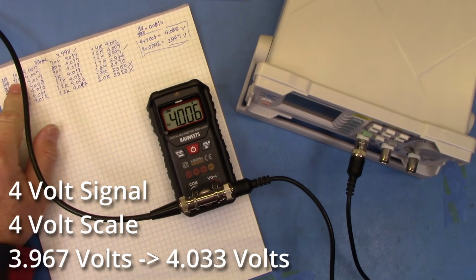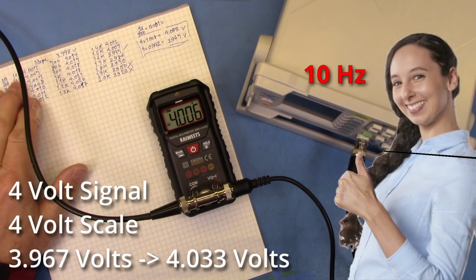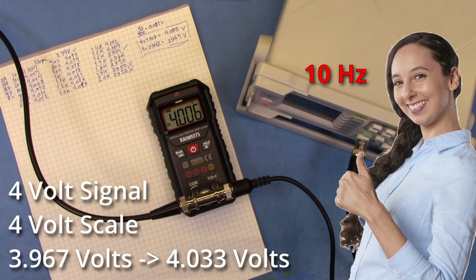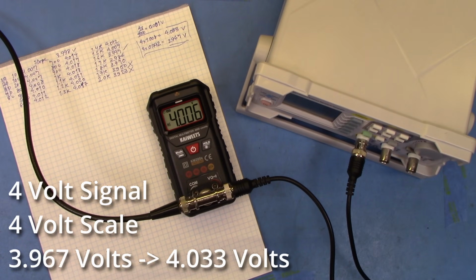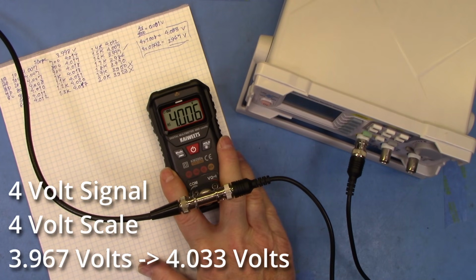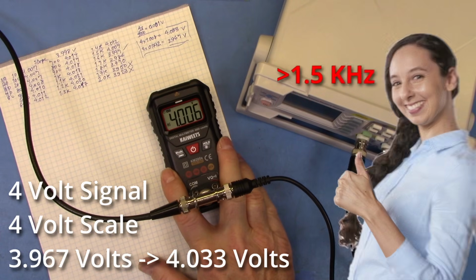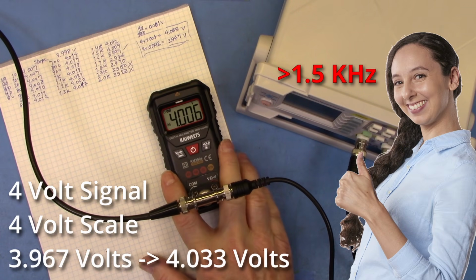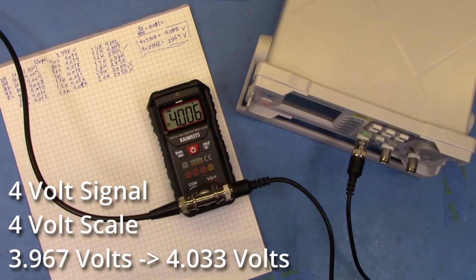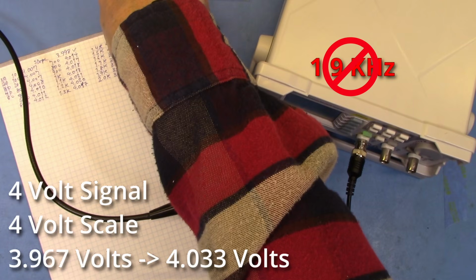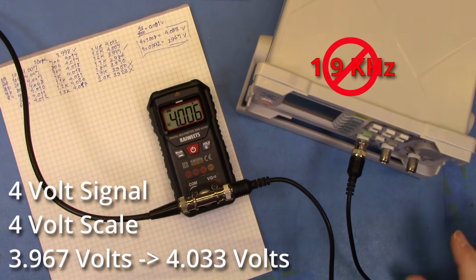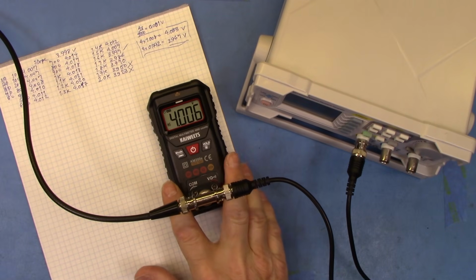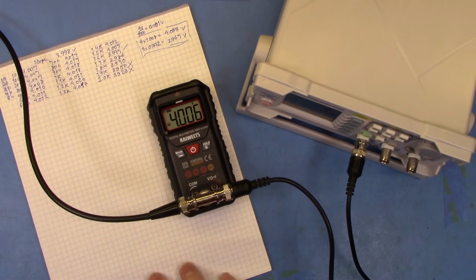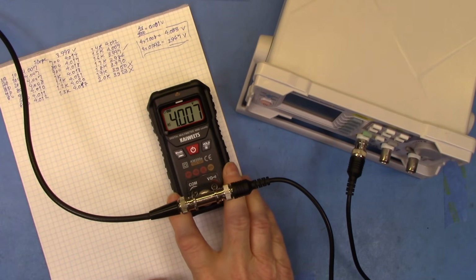So we're assuming the bottom end capability of the KAiWEETS is going to be around 10 hertz. Then from there I moved up in frequencies, and I discovered this meter stayed well within tolerances all the way up to and past 1.5 kilohertz. That's not bad at all. But it dropped out of tolerance at 1.9 kilohertz. Now, with that said, not every meter is exactly the same, so if it were me and I were to buy another one of these, I would assume 1.5 kilohertz is a good upper frequency limit if I want reasonably accurate measurements.